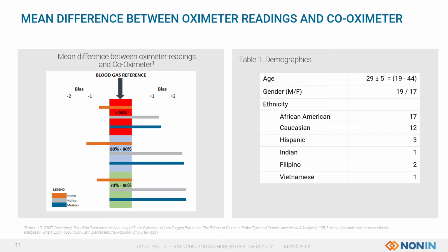Now, bias is the mean of the differences between oximeter reading and the functional SpO2 values, as measured by a co-oximeter from an arterial sample. So positive bias means the test oximeter overestimates saturation, and negative bias means the oximeter underestimates the saturation.